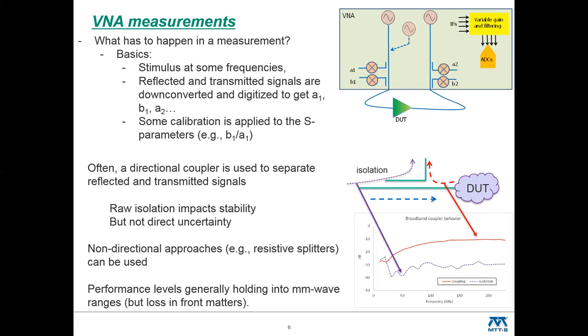One of those is the directional devices, which may be a directional coupler, doesn't have to be, can be a resistive splitter in some cases. This hasn't tended to be a limiting factor too much as we move to millimeter wave measurements; the technology's kept up pretty well. An example here is a broadband coupler intended to cover about 30 to 220 gigahertz, and the coupling factor is higher than the undesired isolation, or the uncoupled direction, over all that range, which is what you'd like to have most of the time. But that hasn't been that much of a limiting factor in terms of how it reacts with stability, and certainly not direct uncertainties.